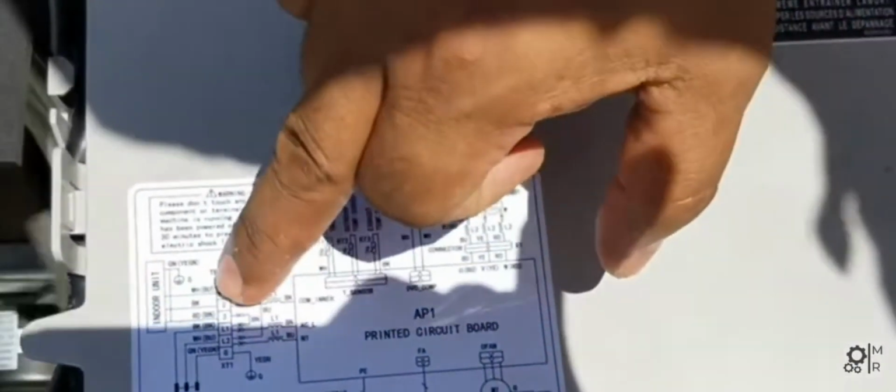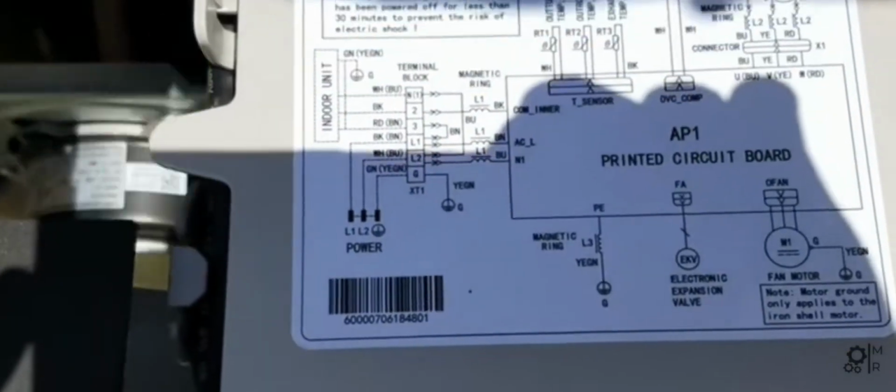Here we can see the card, where the power cables enter, and we do a zoom on each of them. We can see L1 brown, L2 blue and ground, which is the green with yellow. Then here we can see 1, 2, 3 and ground, which are the cables that we saw today that go toward the indoor unit.